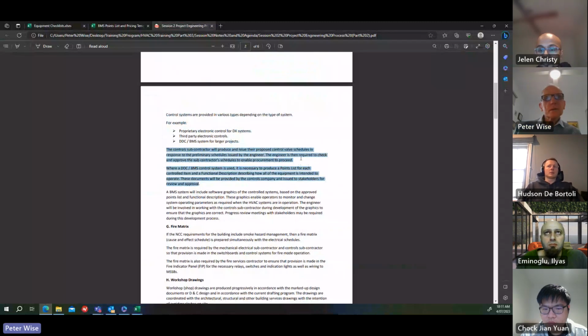The engineer is then required to check and approve the subcontractor schedules to enable procurement to proceed. So this is another point on the road that you can't delay. If you need to check the schedules from the controls people as quickly as you can and give them comments or approval so that they can get on and order the valves, because they may not be ex-stock, they might have to come from overseas, and quite often they do. So it all takes time.